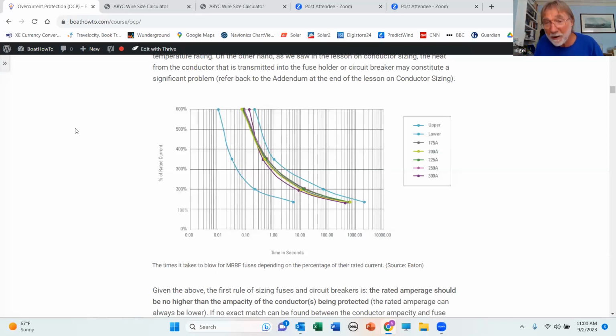And they hadn't sharpened the fire axe. So the guy is hacking away at the cables, and it took him a little bit of time to cut the cables. And then we put the fires out, and everything was actually okay. But the bottom line there is that they didn't have a high enough AIC rating for the potential short circuit currents in the system.